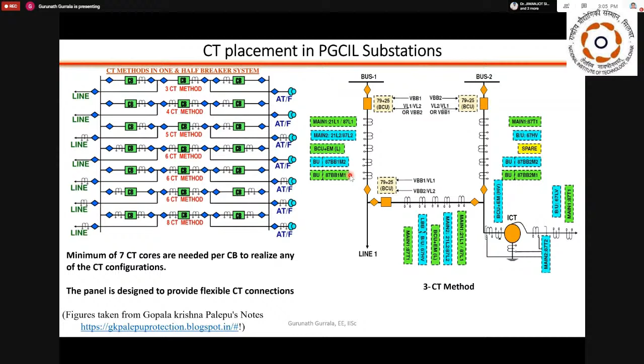This is how my substation looks like. I don't know how many of you understand the single line diagram of a substation. For example, you have bus 1, bus 2, and a transfer bus - 3 buses basically, which are copper or aluminum bus bars that you might see in the field. Each can feed a different feeder, and in this substation we have a total of 4 feeders. I'll show you the complete diagram.